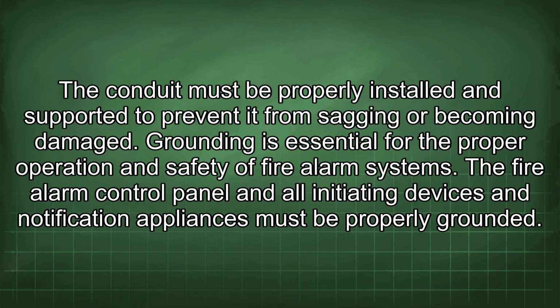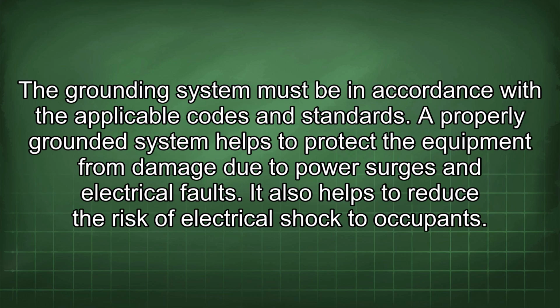Grounding is essential for the proper operation and safety of fire alarm systems. The fire alarm control panel and all initiating devices and notification appliances must be properly grounded. The grounding system must be in accordance with the applicable codes and standards. A properly grounded system helps to protect the equipment from damage due to power surges and electrical faults. It also helps to reduce the risk of electrical shock to occupants.